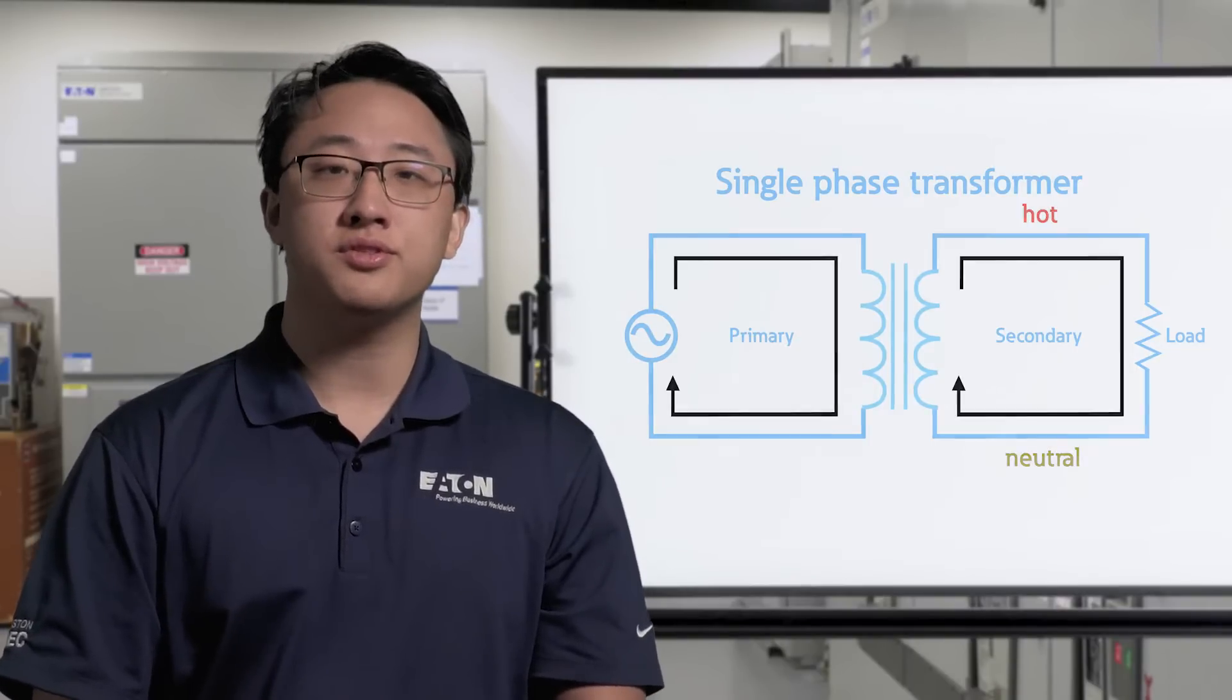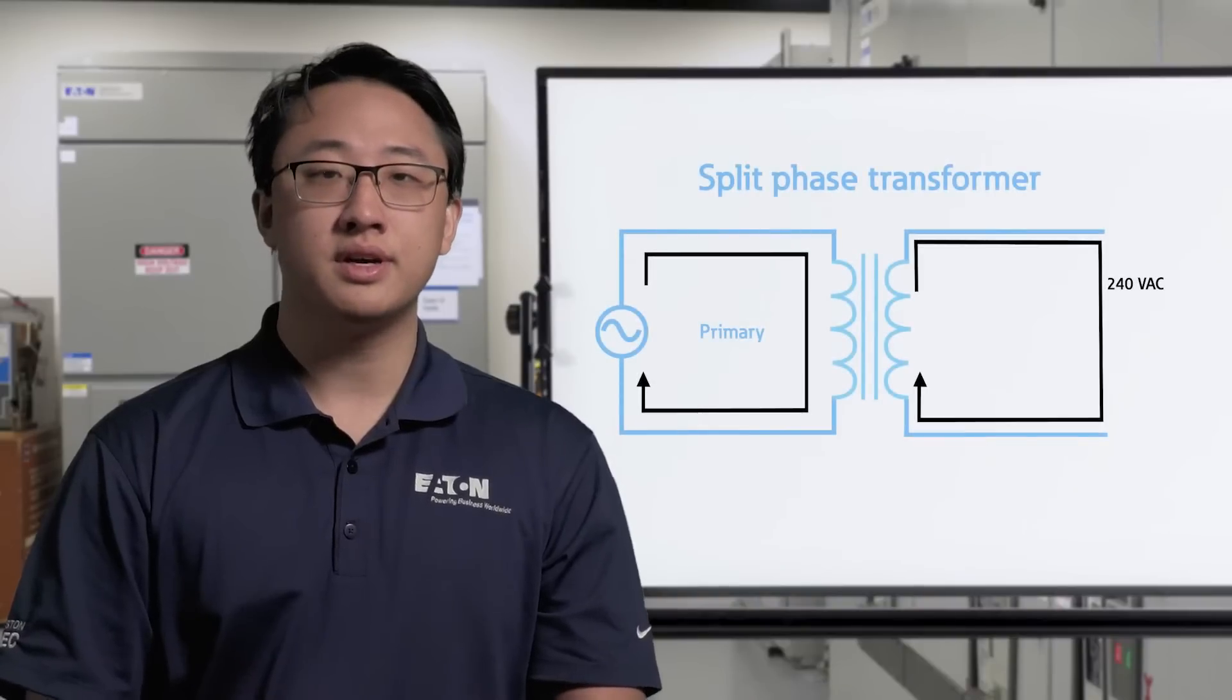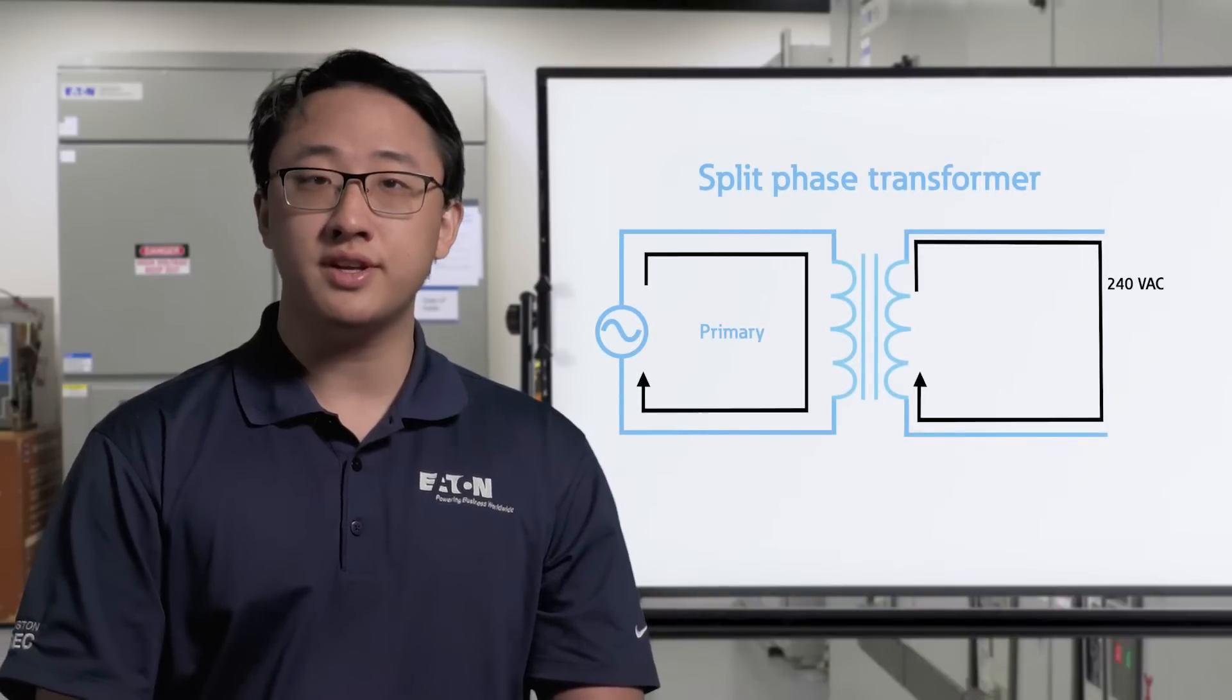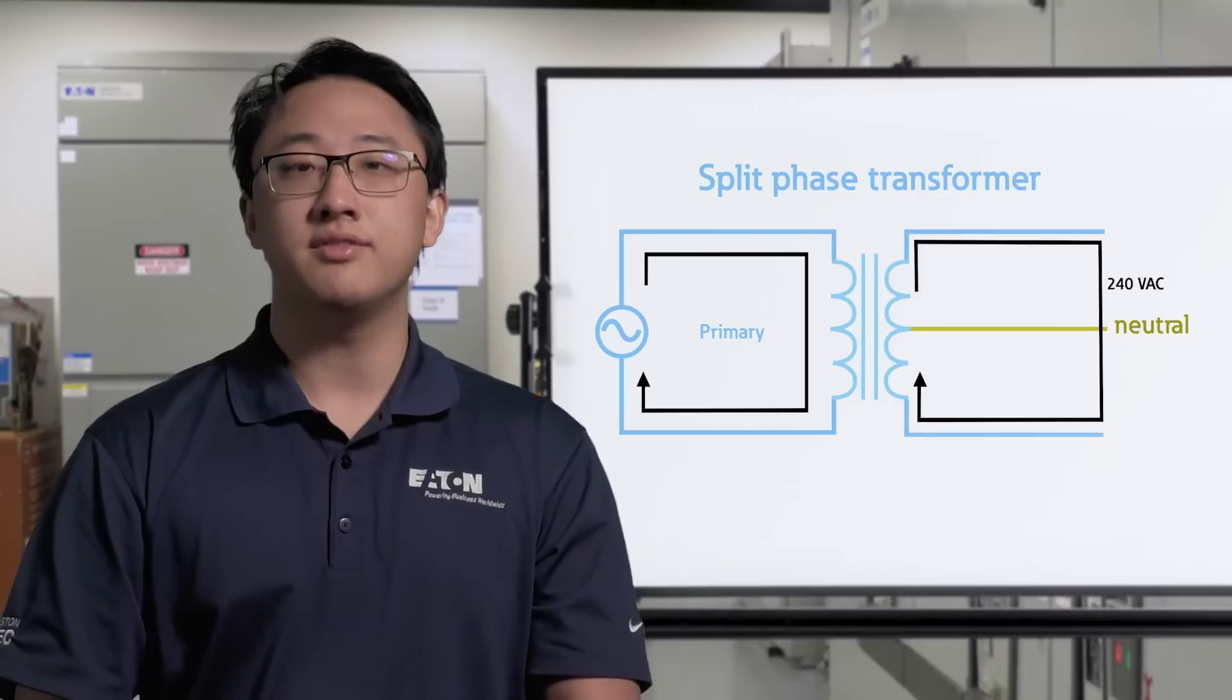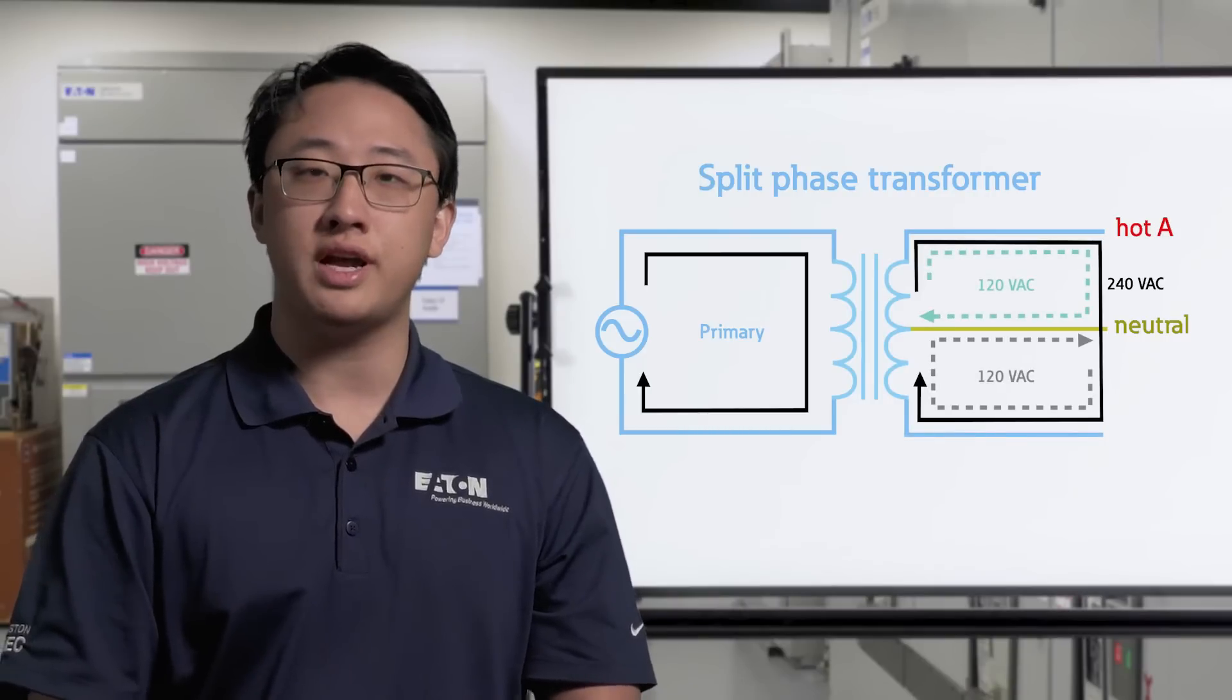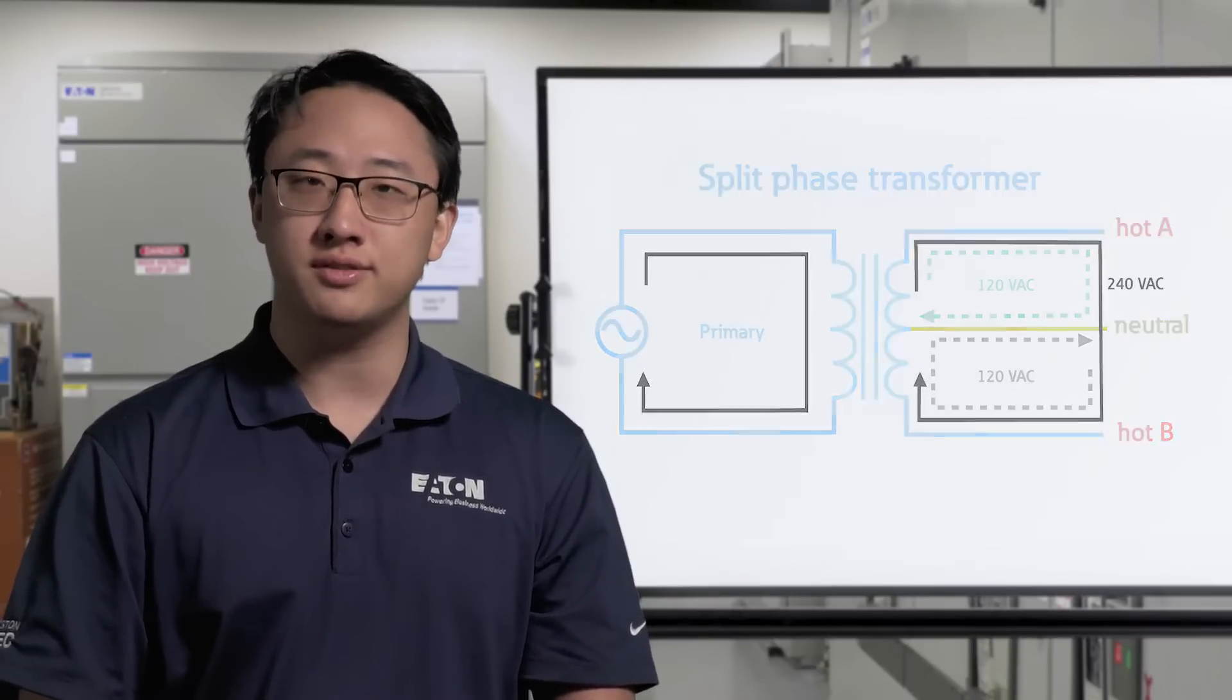Residential systems will use a variation of this single-phase circuit called split-phase. Split-phase will literally split the single phase into half by moving the neutral to the center of the transformer secondary, leaving two separate circuit loops that are 180 degrees out of phase, or one larger loop with twice the voltage.